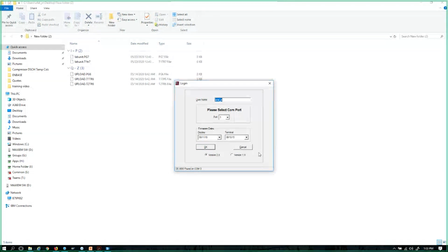So this is one of my favorite screens. I get a lot of phone calls where people can't communicate properly with the DE-3000 for various reasons, but this is the ideal check. When you open up the software, it starts immediately looking for the DE-3000. And in this case, if we view the message displayed in the lower left-hand corner, it says that the DE-3000 was found on COM port 3. It also selected COM port 3 for us automatically.